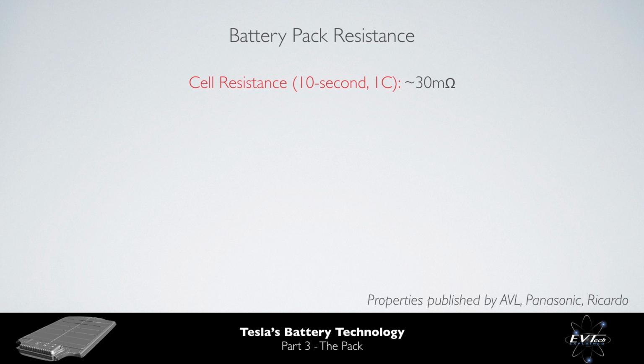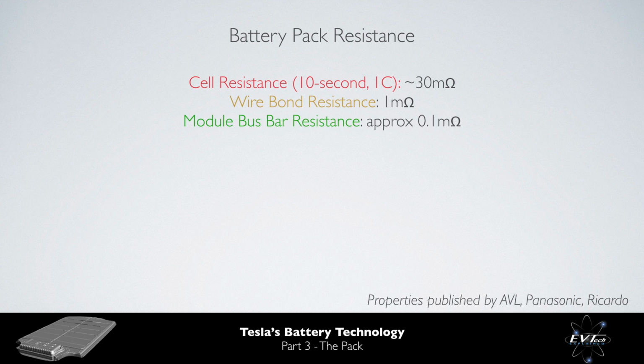Cell resistance is strongly affected by a number of factors, such as state of charge, temperature, and discharge rate. However, for the sake of simplicity, let's work with a value for a 10-second 1C discharge at 25 degrees C of approximately 30 milliohms. The resistance of the wire bond connecting the cells to the bus bars is approximately 1 milliohm per joint, and each bus bar has a resistance of approximately 0.1 milliohms at room temperature.